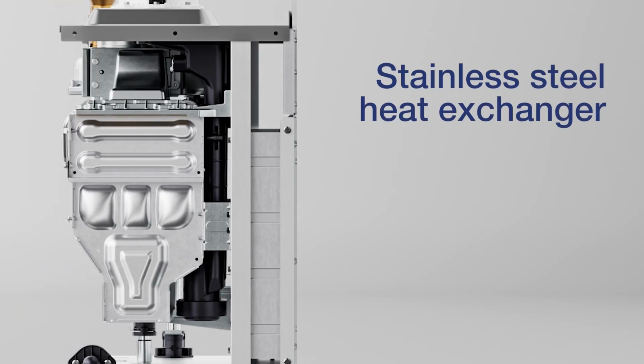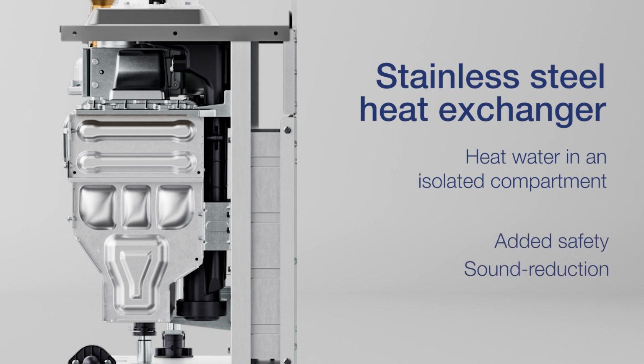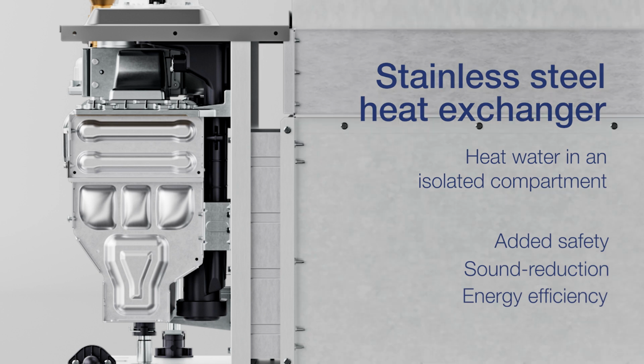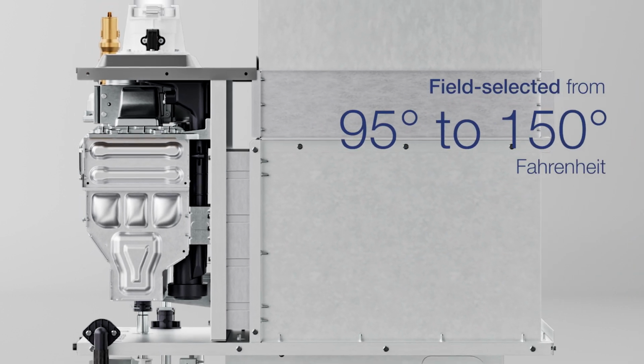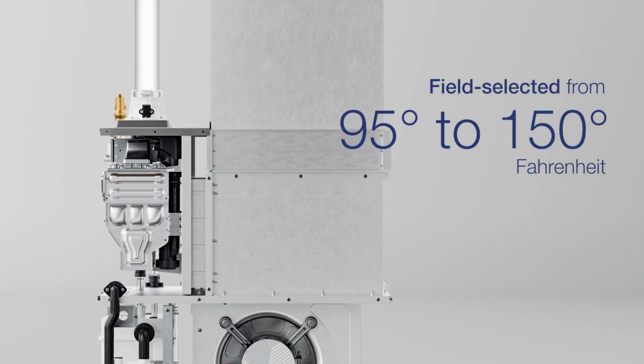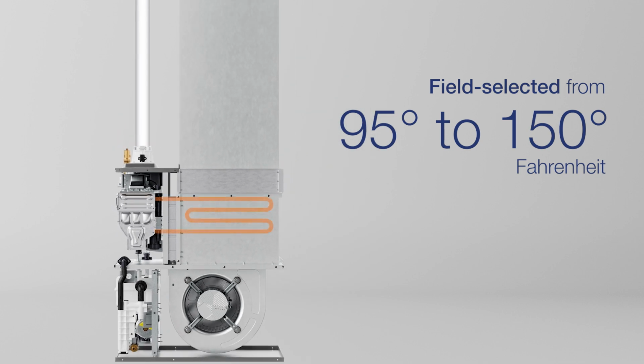The NPF uses its industry-proven stainless steel heat exchanger to heat water in an isolated compartment, really out of the airstream entirely. This provides added safety, sound reduction, and energy efficiency. The supply air temperature can also be field adjusted from 95 to 150 degrees Fahrenheit.